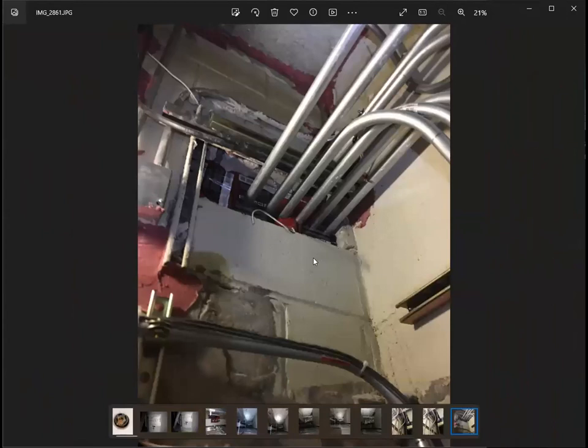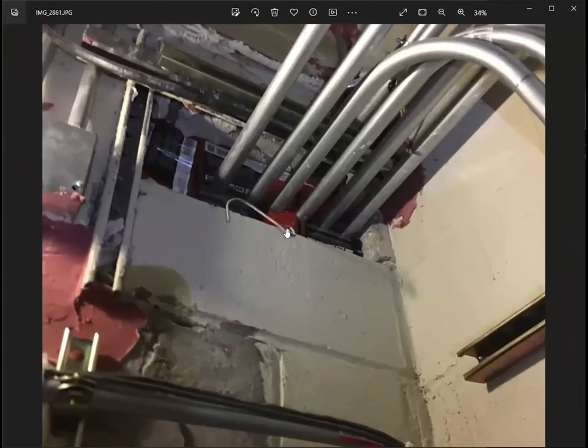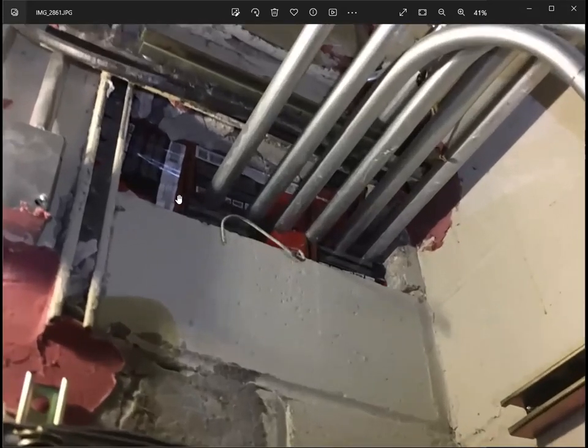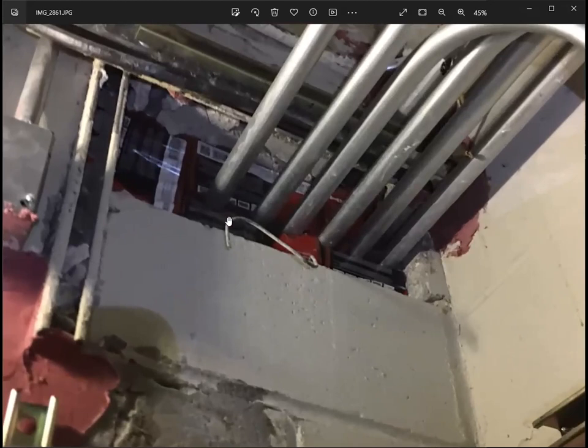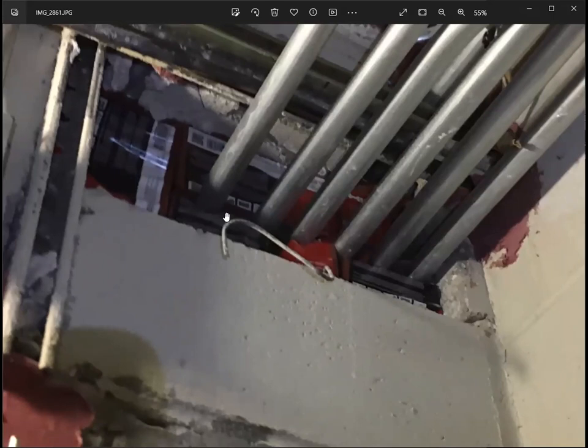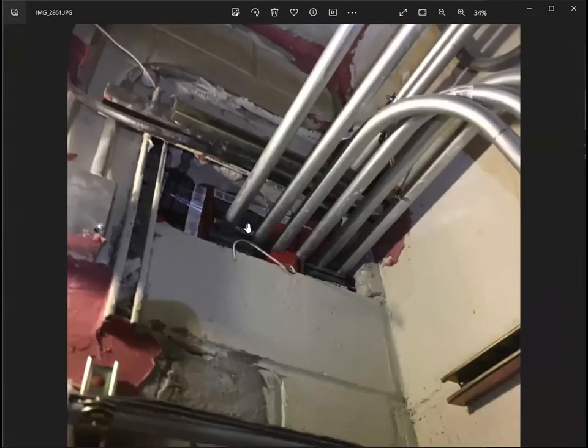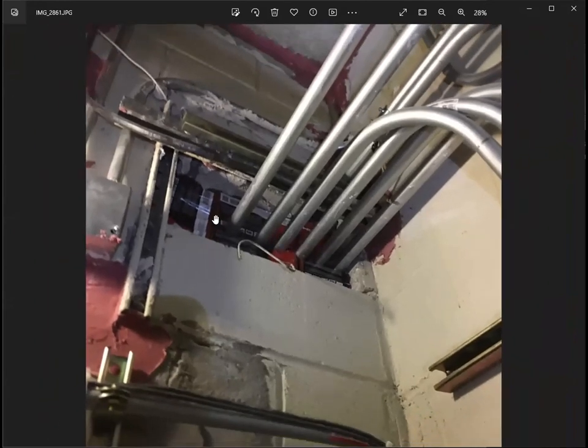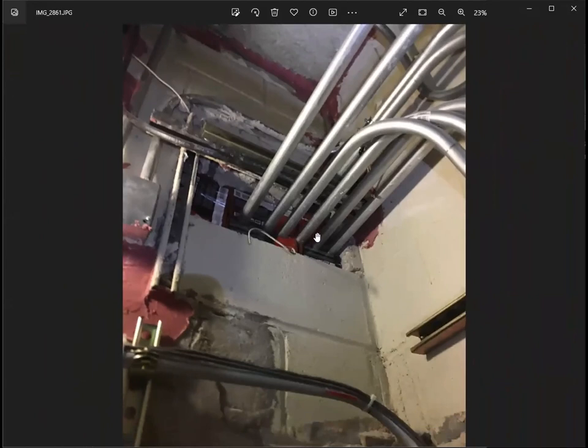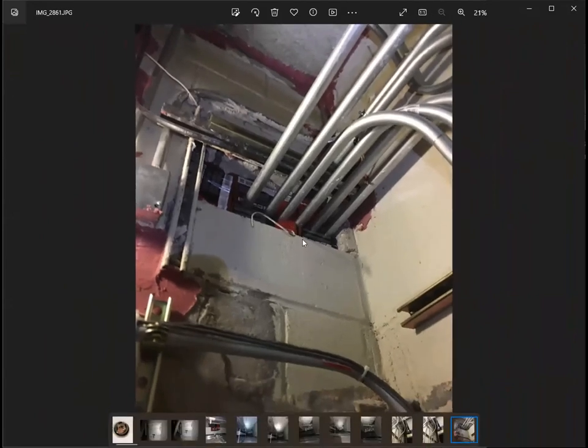Same stuff. So this one, as you can see, you need to see the specs on the drawing, because this is a CMU wall, a concrete wall. A CMU wall is usually 2-hour to 3-hour fire rated, as far as I remember. They broke the wall and put in all this conduit piping, and all they could do is put a fire blocking and fire stopping material right there. They need to seal up the open wall to retain or restore the fire rating of the wall.